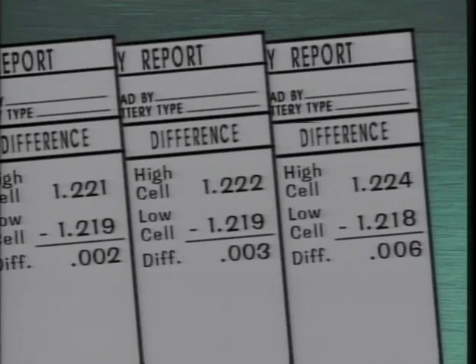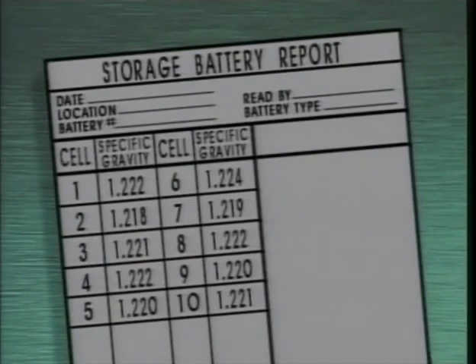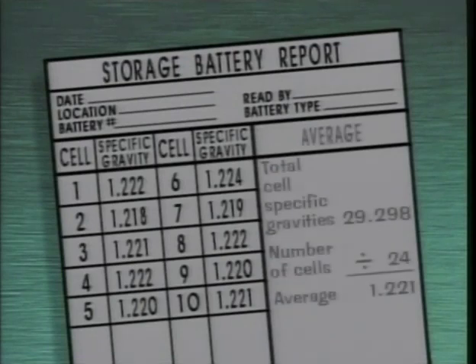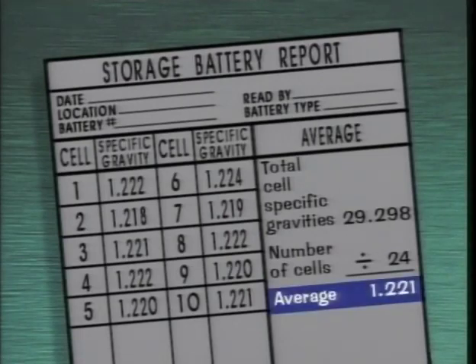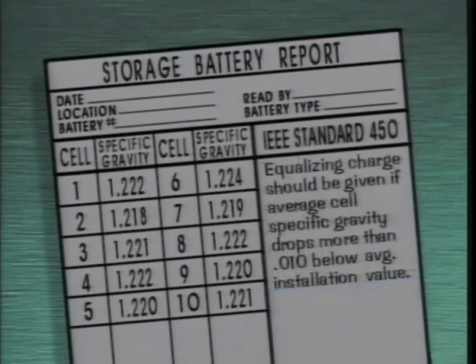Another way to evaluate cell specific gravities is to determine the average cell specific gravity. Each cell specific gravity is then compared to the average. According to IEEE Standard 450, if any cells fall below the average by 0.010 or more, the battery should be put on an equalizing charge. IEEE Standard 450 also states that an equalizing charge should be given if the average specific gravity of all cells drops more than 0.010 from the average installation value.